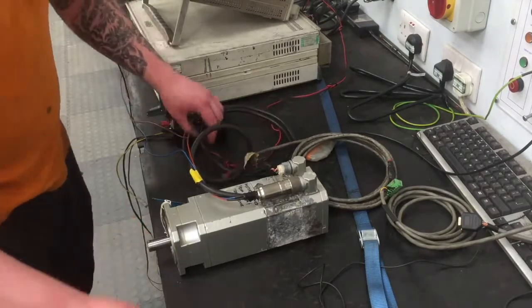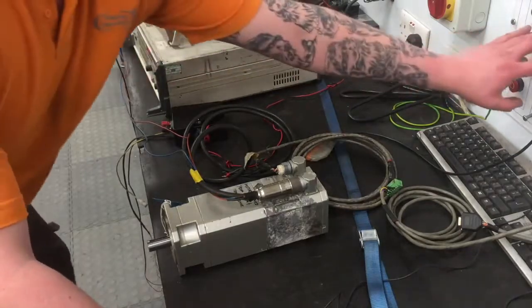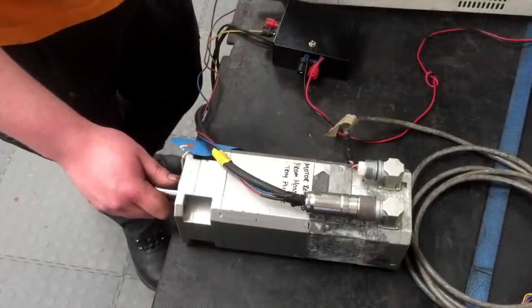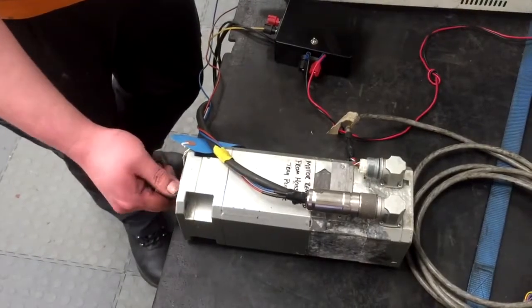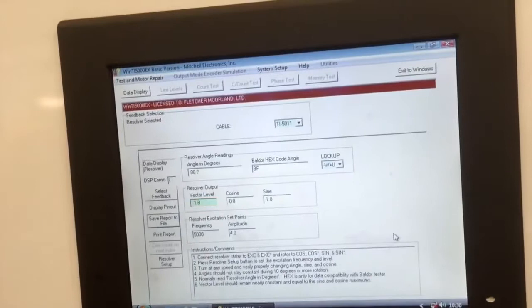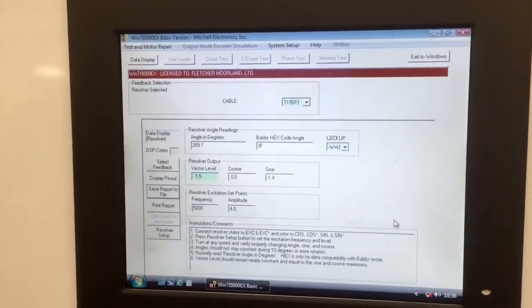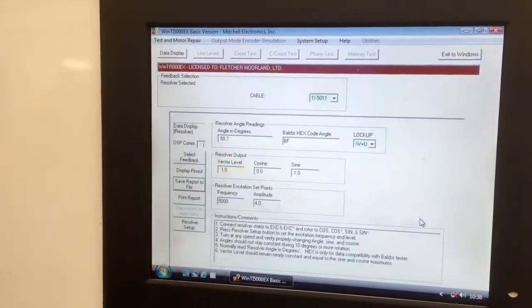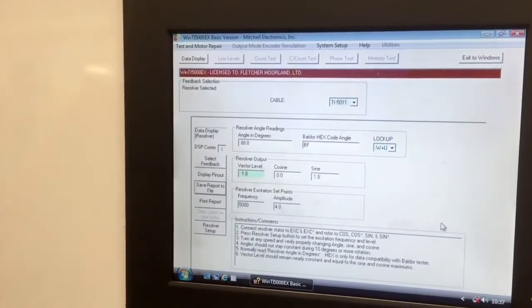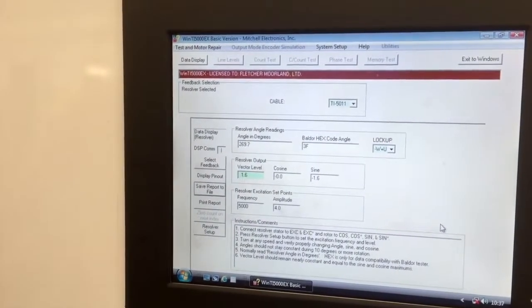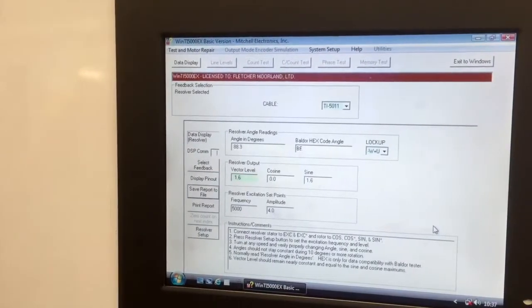The next test that Steve will carry out will be an encoder count test and alignment test. The feedback device for this motor, which is a resolver, has been coupled up to our test rig. We use proprietary software and look at the angle and count test. We can see the vector level is showing an error here and also the angle is not constant. Straight away we have found that there is a fault with the resolver which will need to be investigated further and probably replaced.